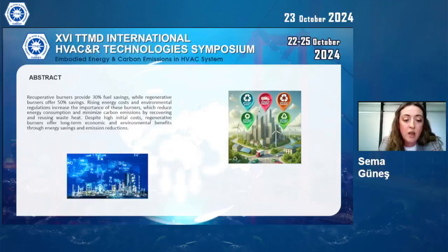Regenerative burners, the most efficient option, with potential fuel saving of up to 50%, thanks to their ability to recover 85 to 95% of the heat from exhaust gas.